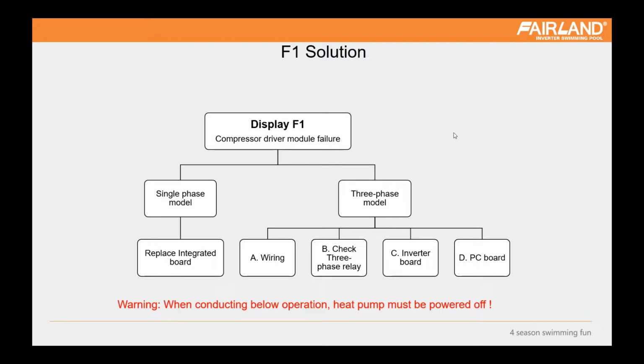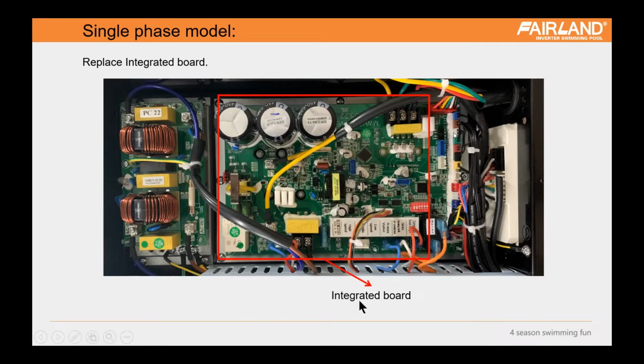And next we will introduce the error codes. This is F1. Because you don't have the three-phase model, here we will just introduce the single-phase model and skip the three-phase part to save your time. F1 is compressor drive module failure. Simply replace the integrated board. Once this code happens, we always suggest resetting the unit. Power off the unit for 10 minutes and restart it to see if it can run normally, because sometimes the code is displayed just for protection, so maybe it can be recovered. But if it's still F1 after resetting, then we have to replace the integrated board.